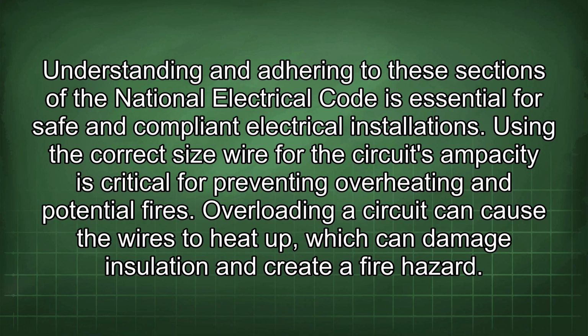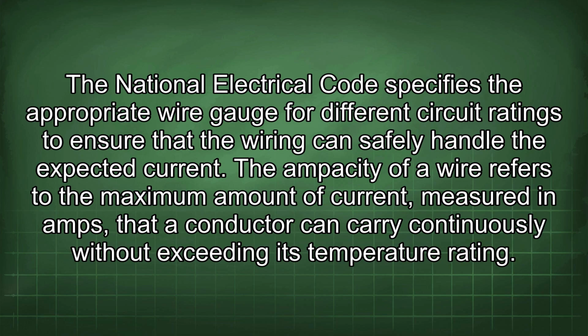Overloading a circuit can cause the wires to heat up, which can damage insulation and create a fire hazard. The National Electrical Code specifies the appropriate wire gauge for different circuit ratings to ensure that the wiring can safely handle the expected current. The ampacity of a wire refers to the maximum amount of current, measured in amps, that a conductor can carry continuously without exceeding its temperature rating.